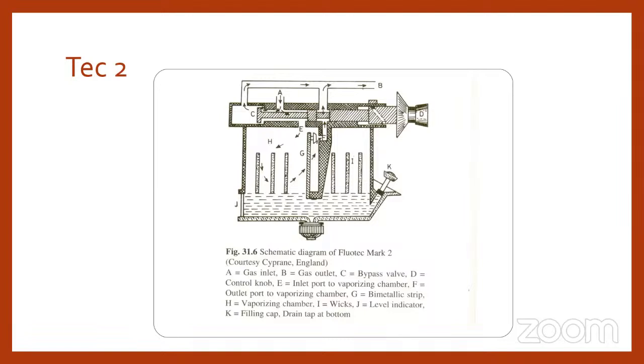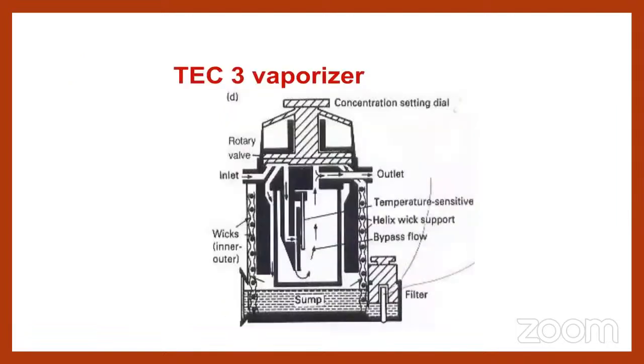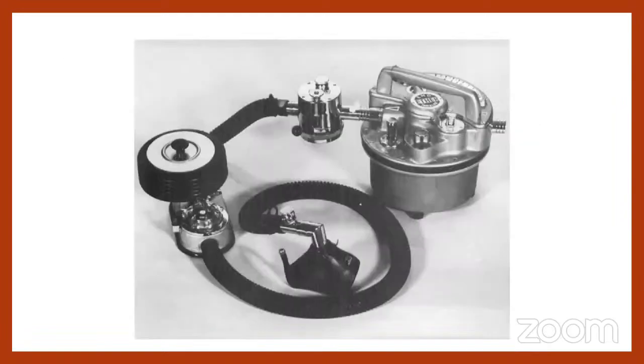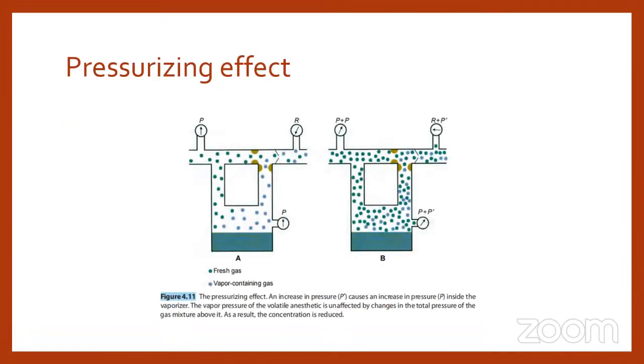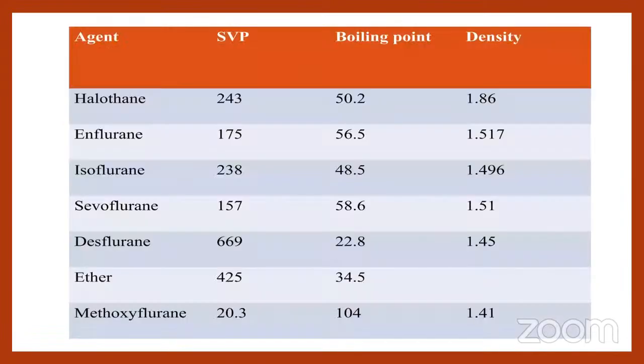And one more thing, you kept a slide on vaporizer saturation pressure or something. Show me that slide. So desflurane has how much percentage? Santosh? Yeah. Desflurane has a boiling point of 22.8, but its saturated vapour pressure, SVP, is very high, very high compared to the other agents. We are using isoflurane and sevoflurane.